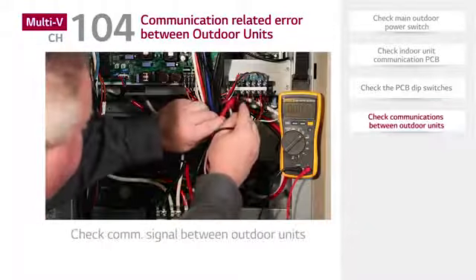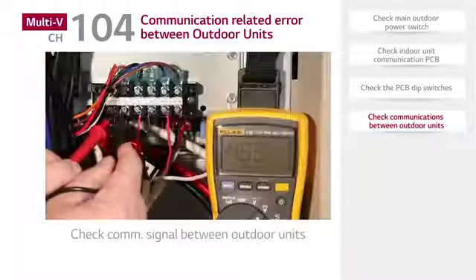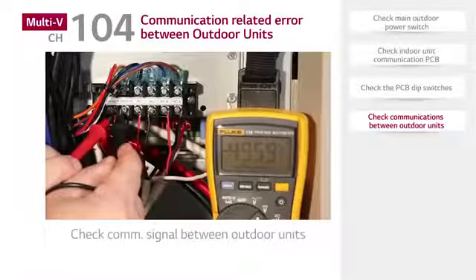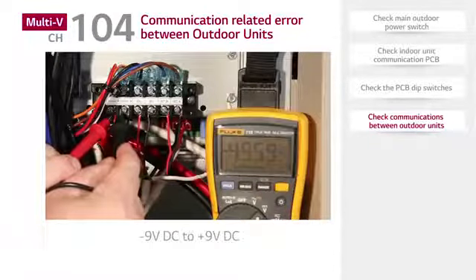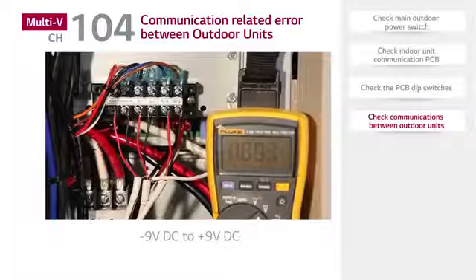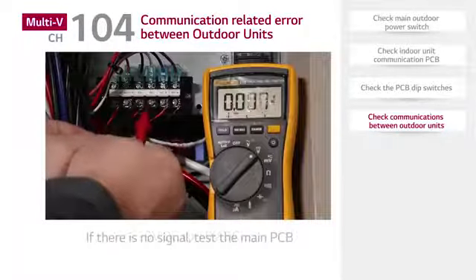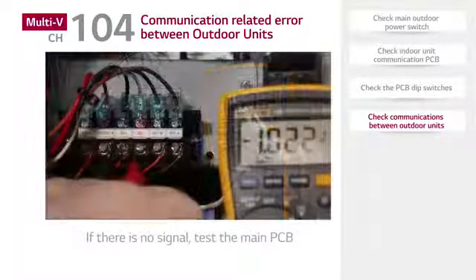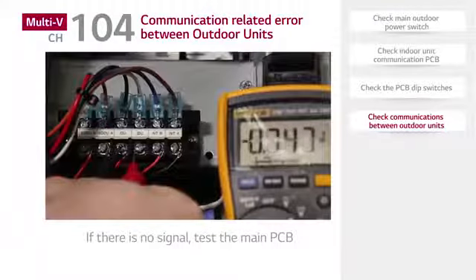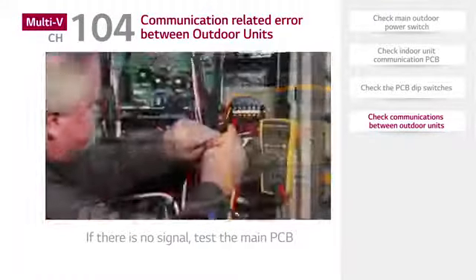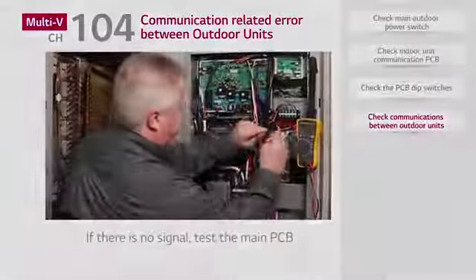If there is no problem with the dip switch settings, check the communication signal between outdoor units. The normal voltage value for the communication signal between outdoor units should vary from -9 volts DC to +9 volts DC. If there is no signal, test the main PCB. If there is still no signal, replace the main PCB.